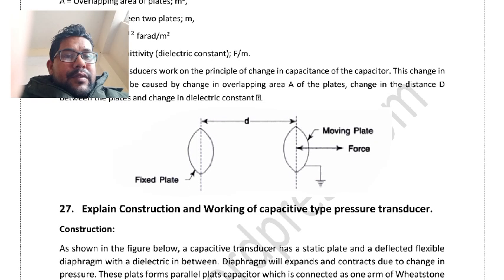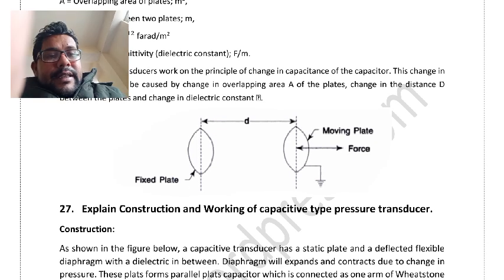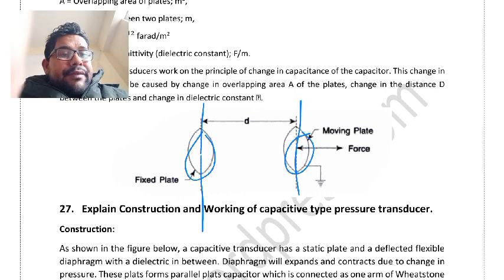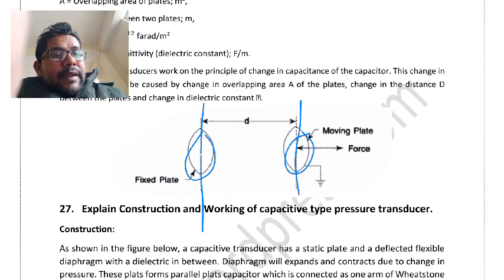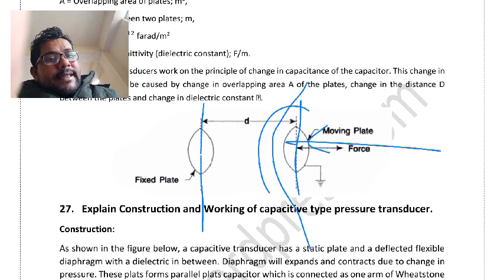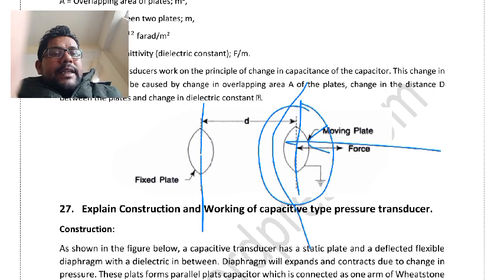This plate is fixed. This is the diaphragm plate, and these outer plates are fixed. Don't confuse this outer part with the diaphragm plate. When pressure is applied on this, the diaphragm plate moves like this, so this distance is going to reduce.